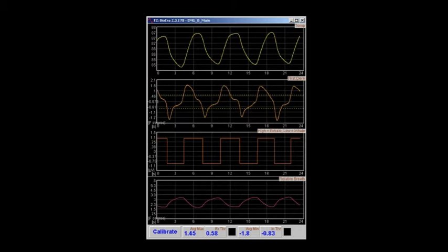If, after this time, the breath trace still doesn't look right, or you get spurious numbers for your breathing rate, then it probably means the system miscalibrated. To correct this, you can either press stop and then start again, or there's a button in the support window here that you press after a short period of even and natural breathing.